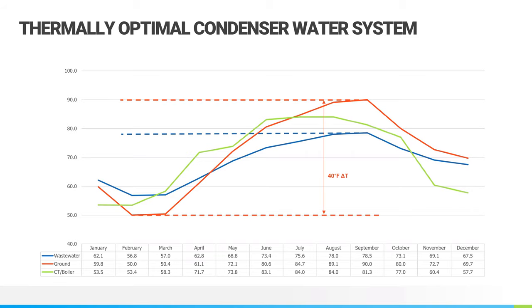So that was one thing that really came out of the system there on site too. Versus the ground, where they had a 40 degree delta between its peak and its low, there's a vast range of temperatures that system would be seeing. And then for the cooling tower boiler, there's a little bit less of a delta. And for the wastewater heat recovery system, it is even less. So by shrinking that band, their system becomes that much more energy efficient.